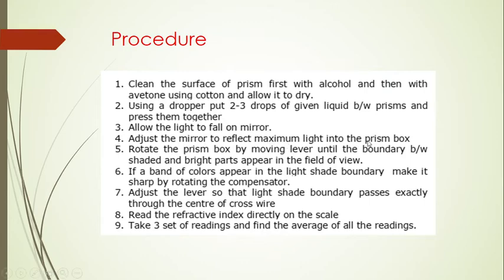Step 4 — adjust the mirror to reflect maximum light into the prism box. Step 5 — rotate the prism box by moving the lever until the boundary between shaded and bright parts appears in the field of view. Step 6 — if a band of color appears, make it sharp by rotating the compensator. Step 7 — adjust the lever so the light-shade boundary passes exactly through the center of the cross-wire. Step 8 — read the refractive index directly on the scale. Step 9 — take three readings and calculate the average.